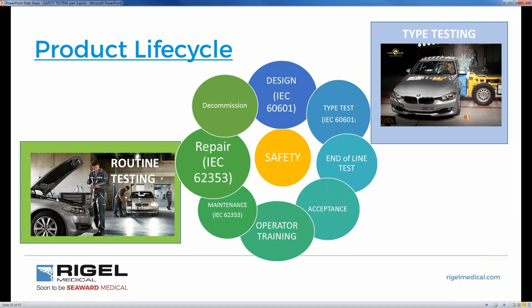But when we take in our car to a service, we want to use in-service testing, which is the 62353. So there's a clear difference between a type test, which is stress testing in the R&D phase to make sure that it is going to be good for creepage of leakage and high voltages. When we do our 62353, it's designed for clinical engineers in hospitals and maintenance. There's a clear definition between the two.